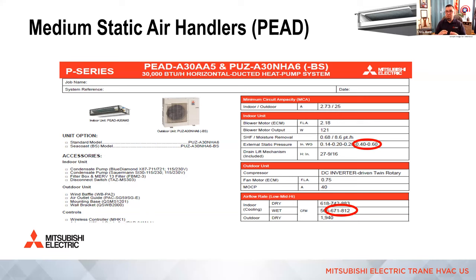So you can see there's three choices when it comes to volume of air, and then there's five choices when it comes to maximum static. So what you want to do with mid and high static heat pumps or furnaces or any other ducted system is choose a mid static rate and medium speed, because this gives your technicians the opportunity to fix a system after the fact, turn the speed up or down, change the static pressure setting up or down. If you design around a maximum, it's really hard for a technician.